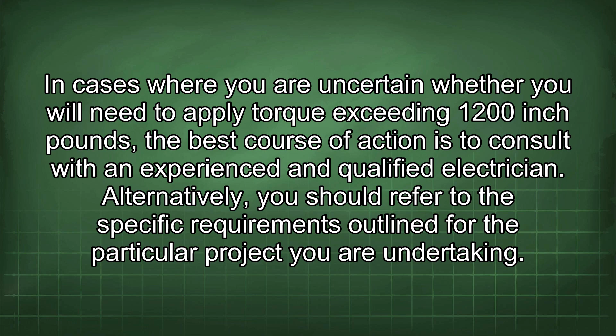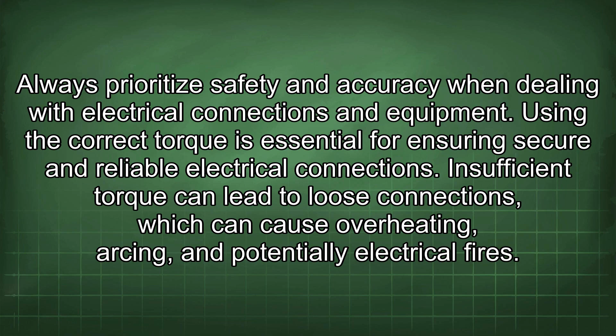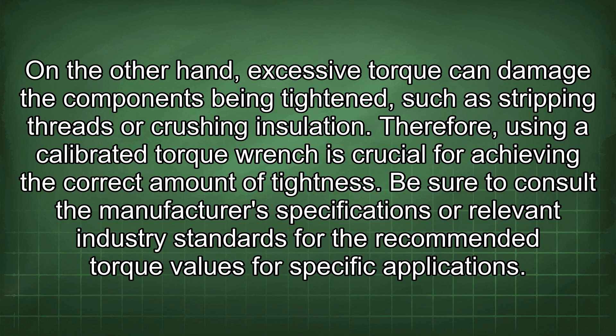Using the correct torque is essential for ensuring secure and reliable electrical connections. Insufficient torque can lead to loose connections, which can cause overheating, arcing, and potentially electrical fires. On the other hand, excessive torque can damage the components being tightened, such as stripping threads or crushing insulation. Therefore, using a calibrated torque wrench is crucial for achieving the correct amount of tightness. Be sure to consult the manufacturer's specifications or relevant industry standards for the recommended torque values for specific applications.